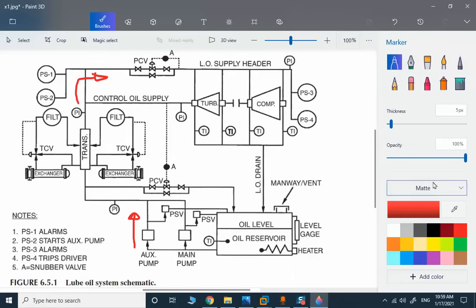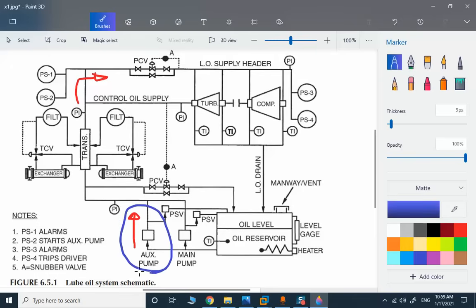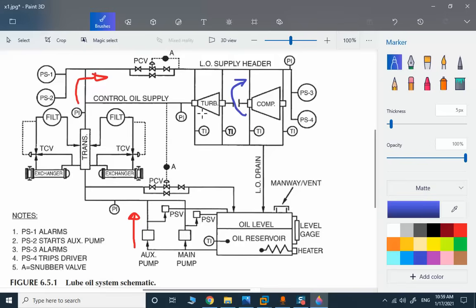For the initial startup of a smaller compressor, the auxiliary pump will be in service. When the compressor is in start mode and we have rotating status, the auxiliary pump will be off and the main pump will be in service. In most cases the main pump is a mechanical component — the pump is connected via a mechanical connection with the compressor.